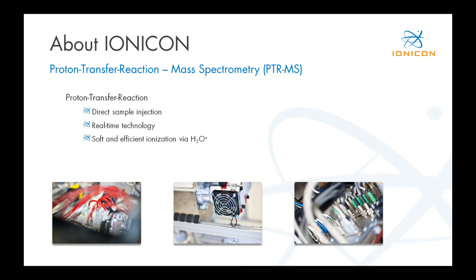First, we have proton transfer reaction. This is an ionization method that uses direct sample injection, so you don't need any sample preparation, and it's a real-time technology — you get your quantitative results on your measurement computer in real-time. It's very efficient and also a soft ionization method, which means you get a quite low level of fragmentation. In case you want to use different reagent ions, such as NO+ or O2+, we call this SRI, and if you even want to use Krypton+, we call this SRI+. SRI stands for Selective Reagent Ionization.